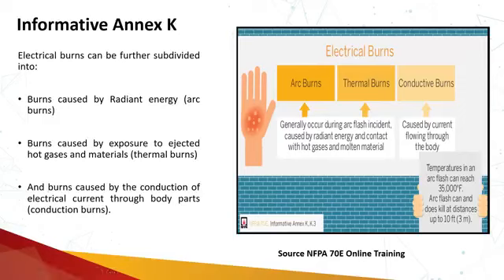So in this type of burn, we will have an entry wound and an exit wound, and there will be a burning of the organs, which will be basically in the path of the current flow. Arc burns basically occur during an arc flash event. An arc flash event is an event in which a high amount of energy is released due to equipment failure, and that is calculated in terms of the incident energy. Once an arc flash event is over, if a person is not wearing appropriate PPE, the burn will continue. The clothes will catch fire, and it will continue to burn for a definite period of time till that arc is quenched.